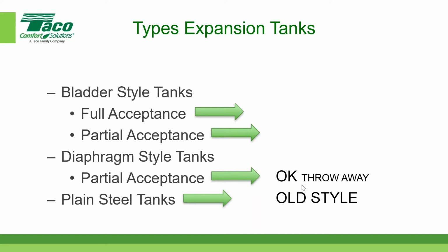Diaphragm style tanks are okay. They work if you size them correctly, but they are throwaways. What I mean is the diaphragm cannot be replaced, so if there's a failure of that component, it's a throwaway. They're okay, they work maybe in smaller systems. I have some good friends on the rep side of the business who say maybe 20 to 50 gallon type systems, they'd suggest you put in a diaphragm. And there are price differences too - you have to get into all of that as well.